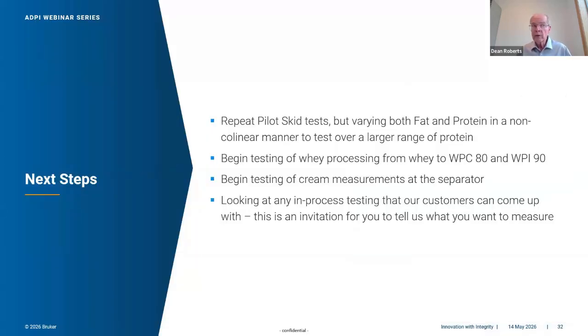So what this looks like to us, at least for fat and total solids, is that using those benchtop calibrations is going to work, provided we know the temperature and that we can apply a different slope and offset correction to account for the temperature difference between the benchtop calibrations at 4 degrees C and what we're actually measuring these samples at. If we're in a process where you're using a heat exchanger, it's a pretty good given that the temperature is not going to have much of an impact. We can't really say for sure that we're going to get the same temperature when we're looking at milk receiving, because each one of those tanker trucks is going to come in at a different temperature. So we may have to put a temperature sensor in line and then dynamically apply a slope and offset to the predictions that come in to try and normalize that for the temperature differences.